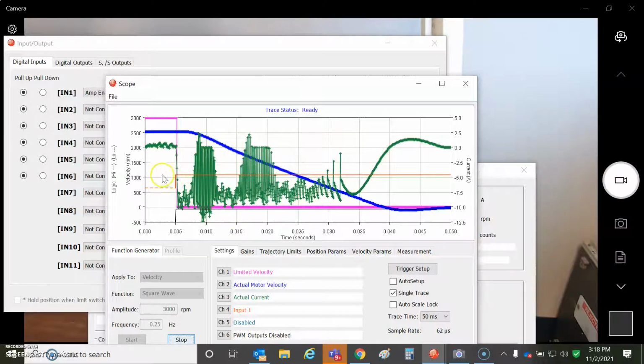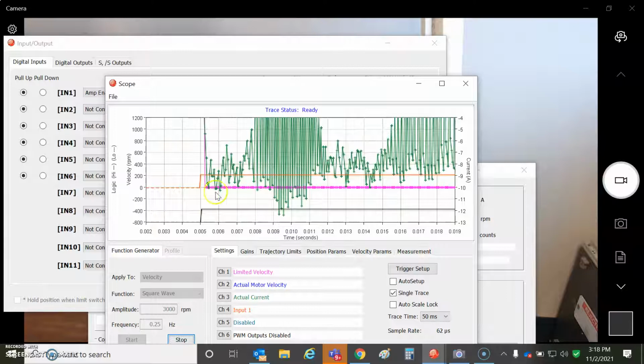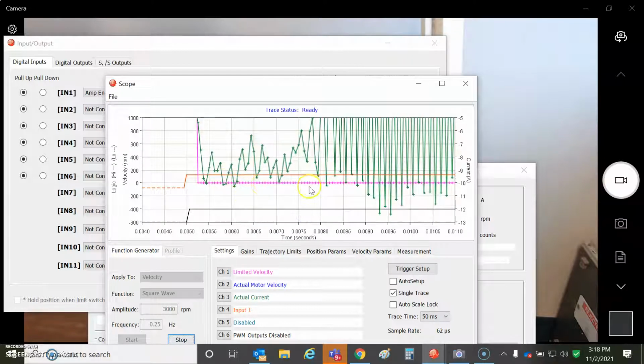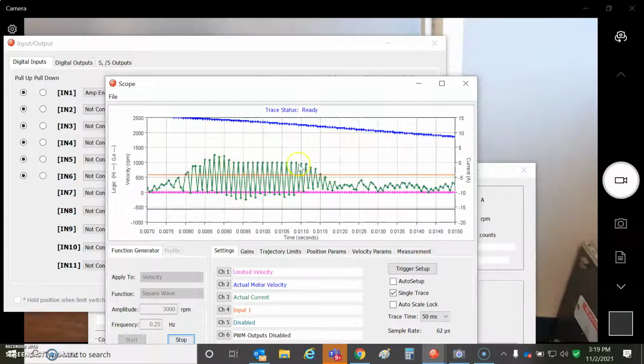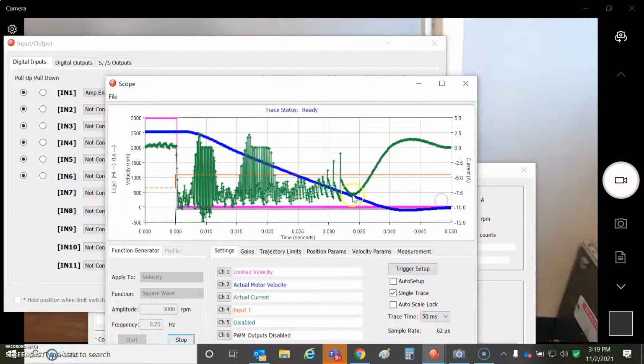Anyways, you can see that it's trying to control the current by shorting, but when you short a motor winding, the current will try to shoot to 150 amps, but then as we measure the current every 62.5 microseconds, we can fold it back. So that's what's happening here: it says, hey, whoa, measured minus 12 amps. So turn it off. So it starts turning it off to zero and then back on again. And it's only limited by the inductance of the motor. There's a slew rate limit, so it's only possible to change the current so fast in 62 microseconds. And then it's coming to a more controllable area.